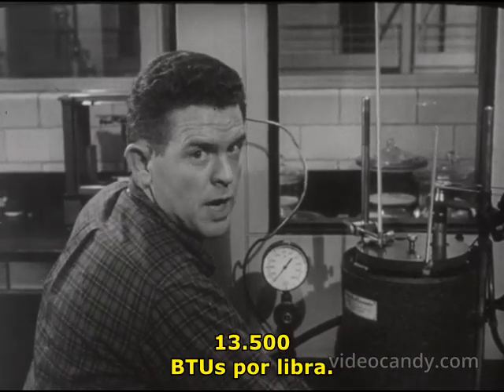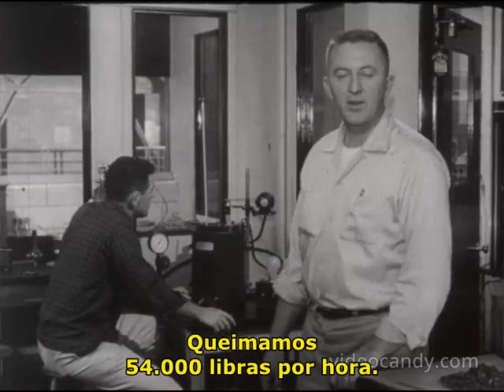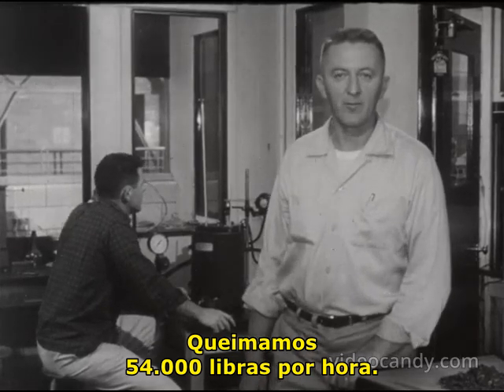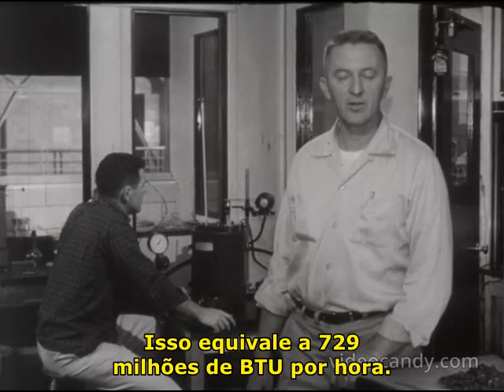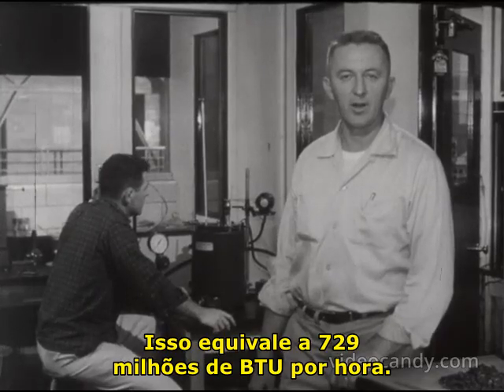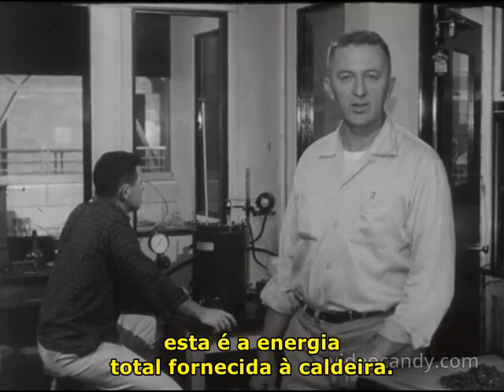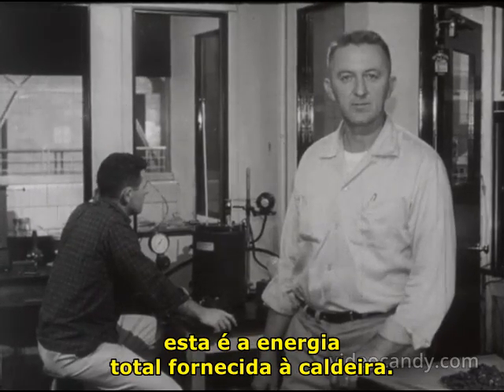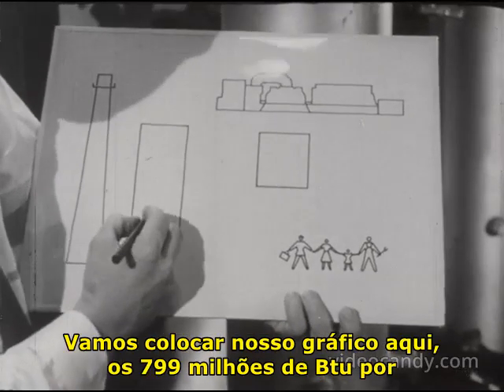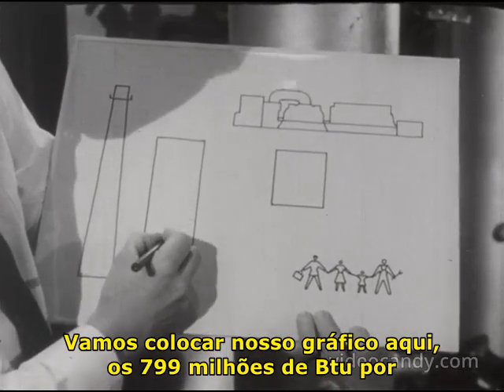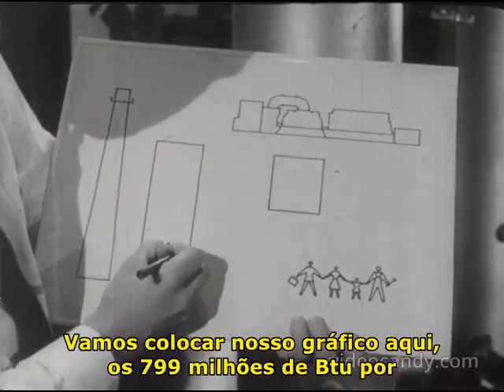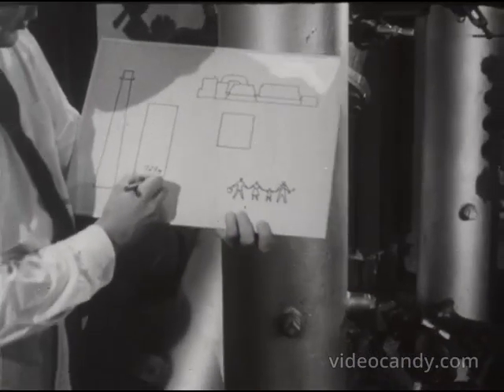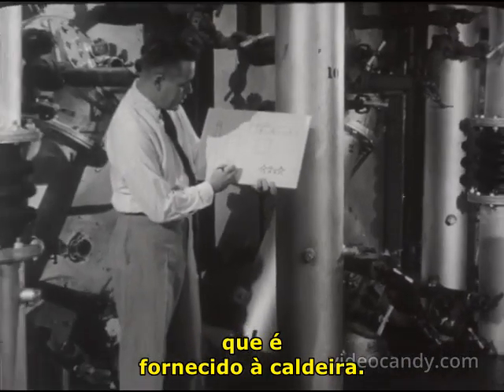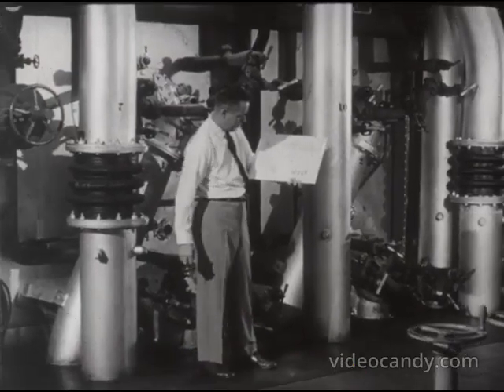13,500 BTUs per pound. We burn 54,000 pounds per hour. This amounts to 729 million BTU per hour. This is the total energy supplied to the boiler. Let's put on our chart here the 729 million BTU per hour, which is supplied to the boiler.